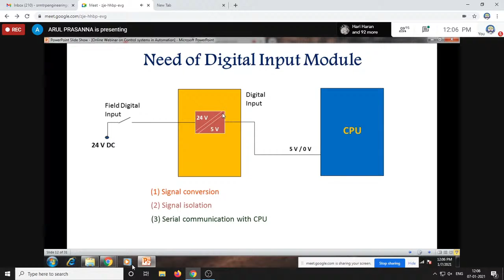Your input module performs some additional functions: signal conversion, signal isolation, and serial communication. Serial communication means through voltage, we can communicate with the CPU and with the field device.